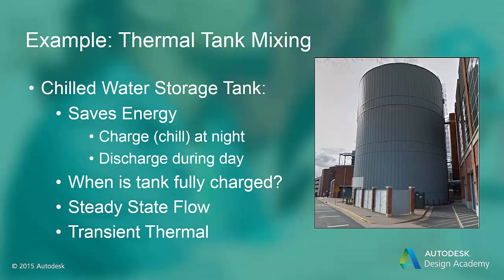Another type of unsteady flow analysis that is frequently performed is when the flow or velocities are steady, but the thermal or heat transfer is transient. We use this type of unsteady problem setup for a chilled water storage tank, which is part of a large chiller plant. The chiller plant provides air conditioning for a hospital complex. The storage tank is used to reduce chiller cost. The tank is pumped full of cold water at 40 degrees Fahrenheit during the night hours — this is the charging cycle. Then the tank is discharged to provide chilled water during the daytime hours.